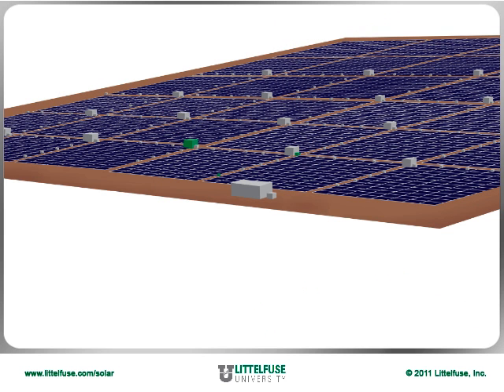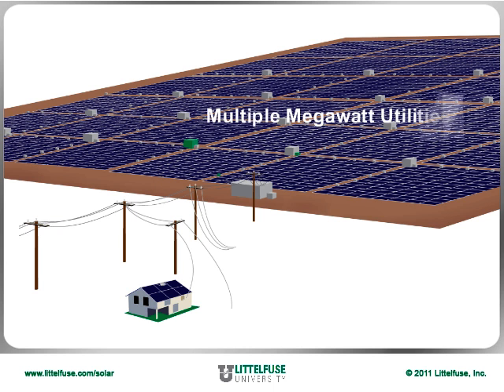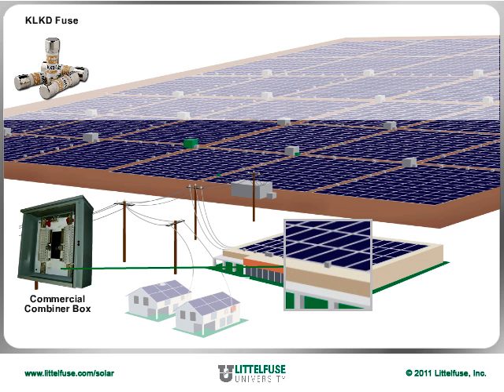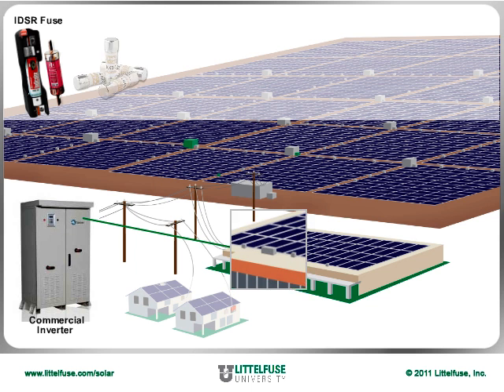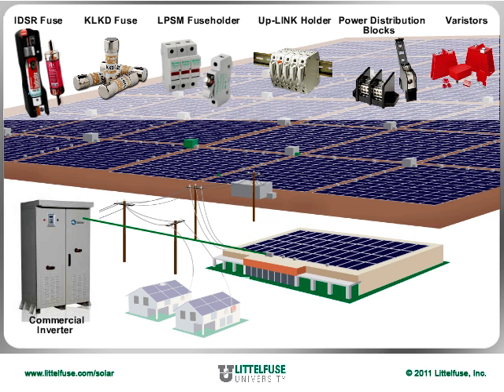Power inverters take all this DC electricity and turn it into AC power, which is then consumed to meet users' various power needs. Applications range from PV systems as small as 1 kW for residential homes, to multiple megawatt utility systems designed to power hundreds of homes and businesses. Commercially used combiner boxes utilize KLKD midget fuses with uplink or LPSM touch-safe fuse holders, the bus bar systems for the LPSMs, and power distribution blocks. Commercial inverters use IDSR and KLKD fuses, LPSM or Up-LINK holders, power distribution blocks, and varistors.